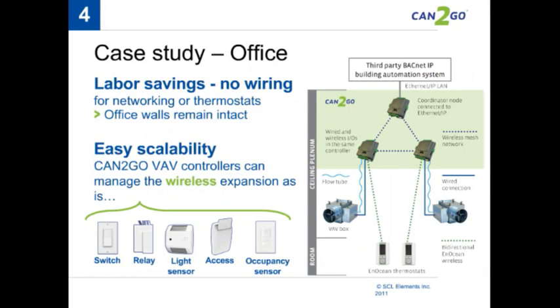What was actually installed was a couple of controllers meshed together wirelessly with Zigbee, so they didn't have to run networking wires between controllers. This connected over Ethernet and IP LAN to the third-party BACnet IP system. Every controller connected to a VAV box, and each VAV box allowed local occupants to adjust their set point with an EnOcean thermostat, which is also a wireless end device.